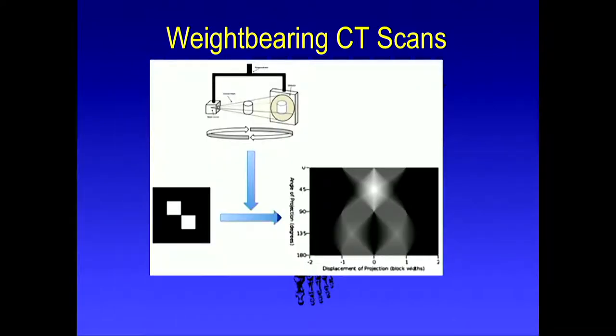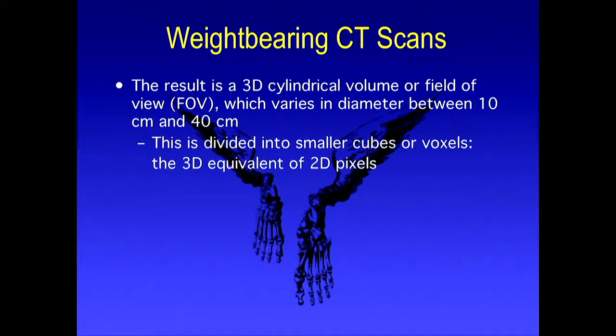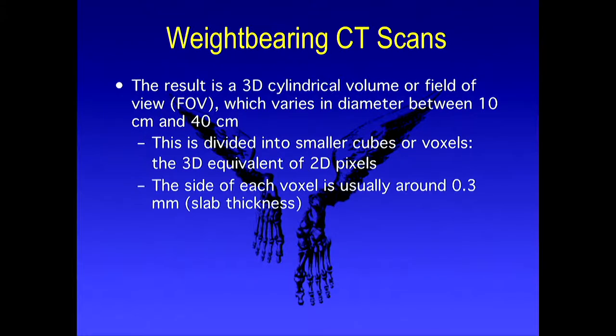You place the machine, do the scan, and it takes about two minutes as opposed to a normal CT — really fascinating. The result is a three-dimensional cylinder of volume, or field of view, varying in diameter between 10 cm and 40 cm. This is divided into smaller cubes called voxels. A voxel is the 3D equivalent of the pixel on your phone — that's the best way to think about what you're getting.